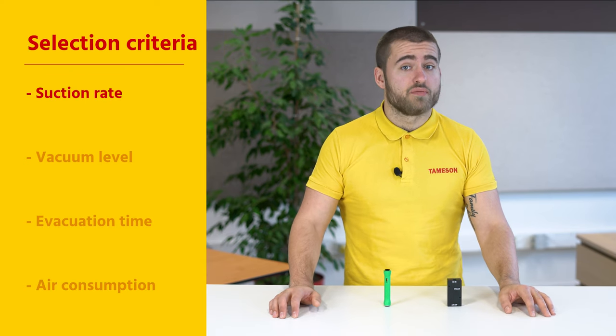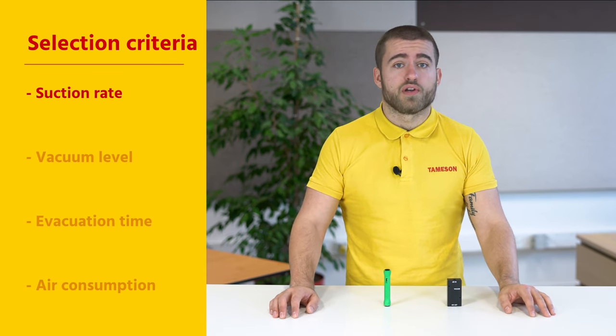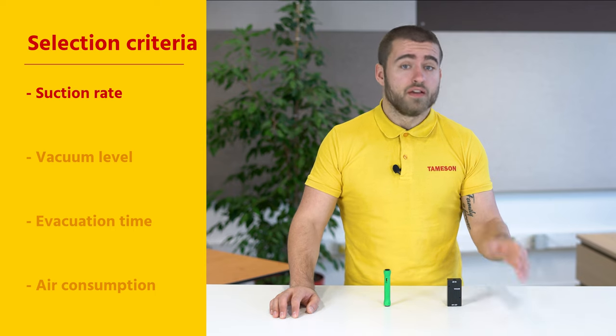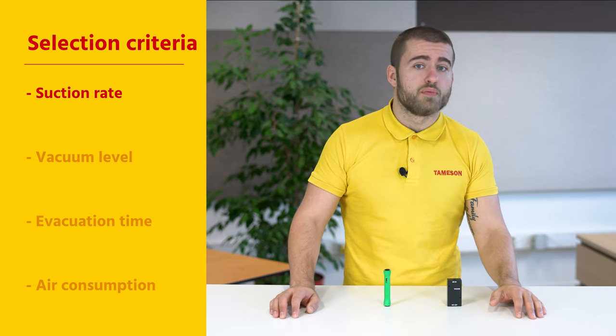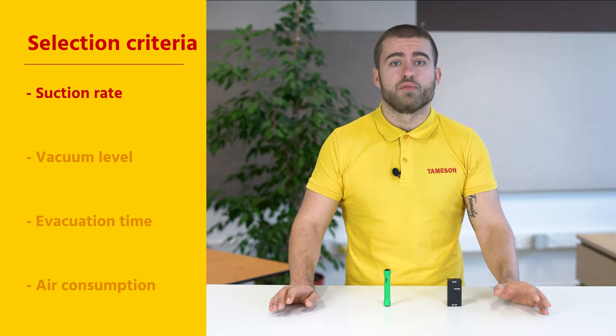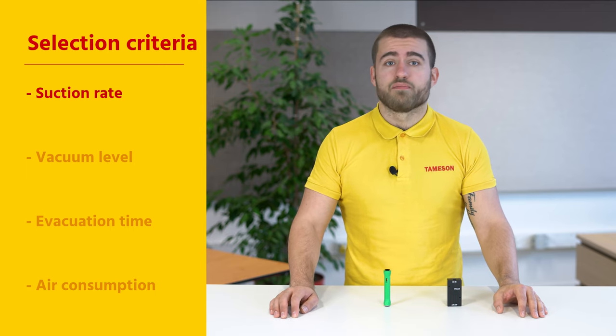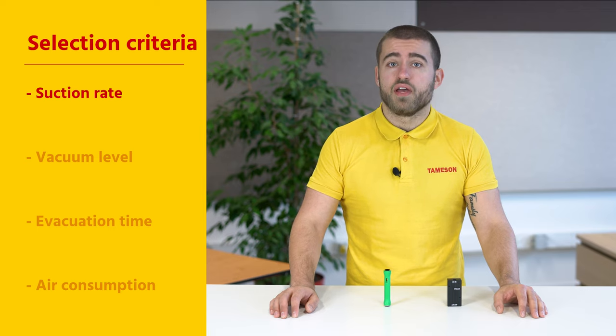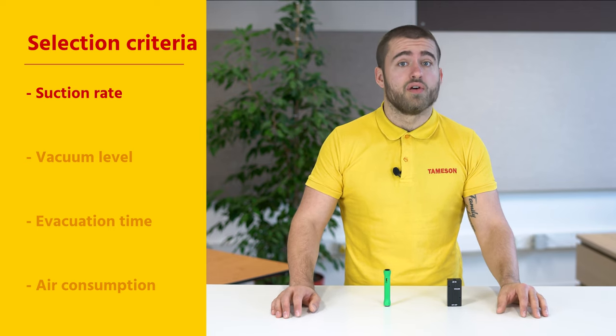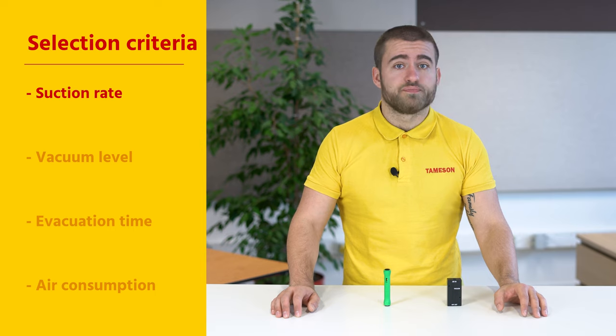When selecting a vacuum generator, it is important to take the following criteria into account. The suction rate is usually defined in cubic meters per hour or liters per minute. The maximum suction rate is defined as the maximum flow rate that the vacuum generator evacuates from the environment, and this is free flow, so the flow rate is different when something is picked up.